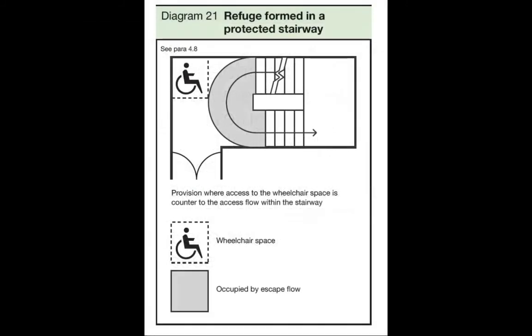Important thing when you're thinking about fire design: never refer to the Arts Tower, because the Arts Tower is a complete anomaly. None of it is compliant with the guidance. It's compliant through fire engineering and a lot of very tricky compromises. None of it is by the book. So don't think, well, there are no refuges in the Arts Tower.